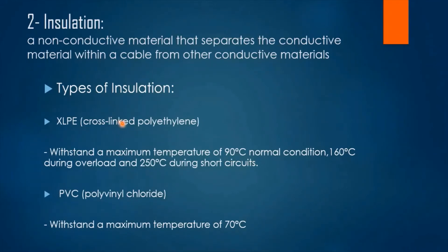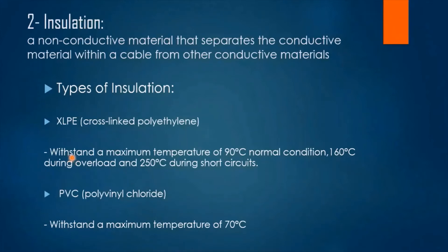The second layer of the cable is the insulation layer — a non-conductive material that separates conductors from each other and from other conductive materials. We have two types of insulation: XLPE (cross-linked polyethylene) and PVC (polyvinyl chloride). XLPE can withstand much higher temperatures than PVC — up to 90°C under normal conditions, 160°C during overload, and 250°C during short circuits.